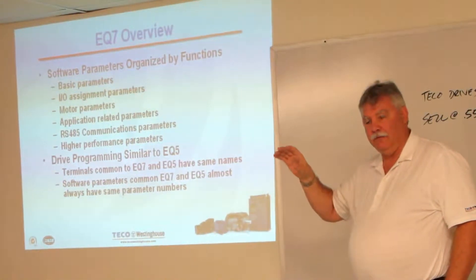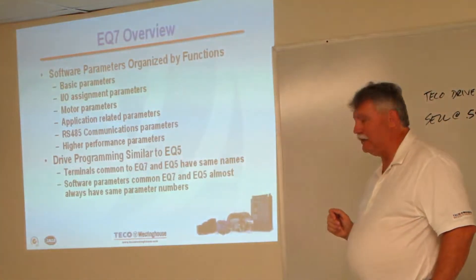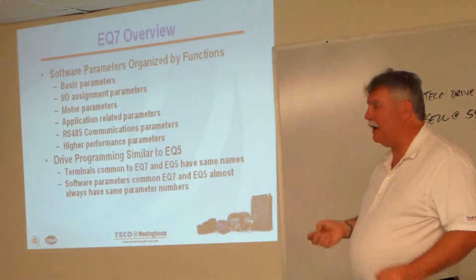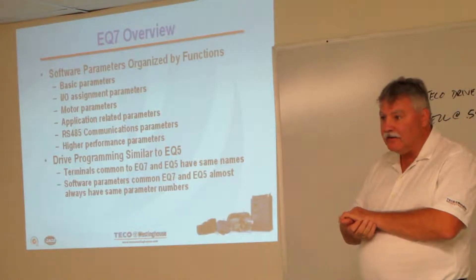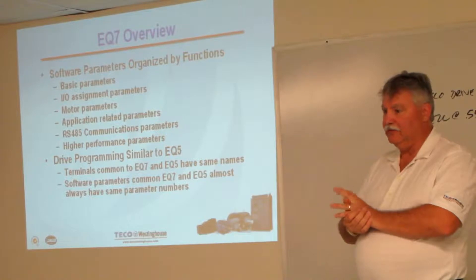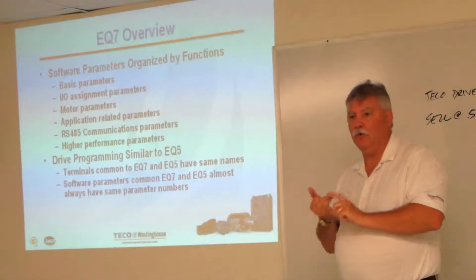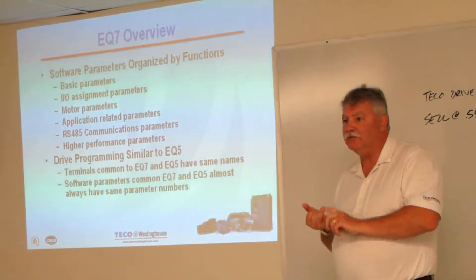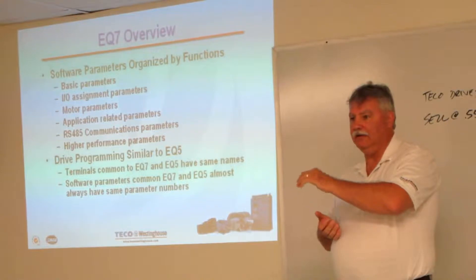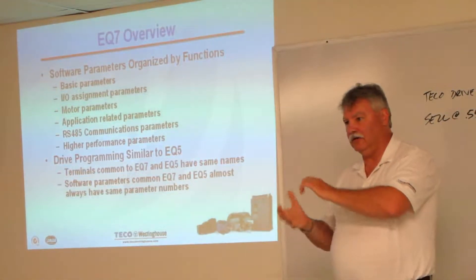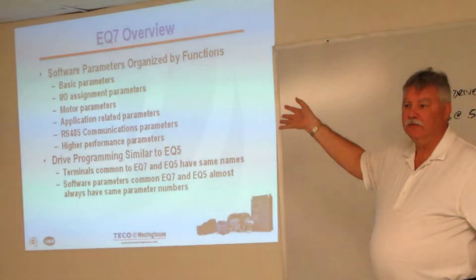If you want to start from the keypad or from a remote switch, those are the basic parameters. The next set is IO assignment. The drive has nine digital inputs, six digital outputs, and a couple of those digital outputs are relay and contact outputs. So you have some possibilities for coordinating things like doing some switching on the fly, some interlocks. You can use a contact to say the drive is at speed, or use another one in case the drive trips out on a fault — you need to send that information out. You have that capability.